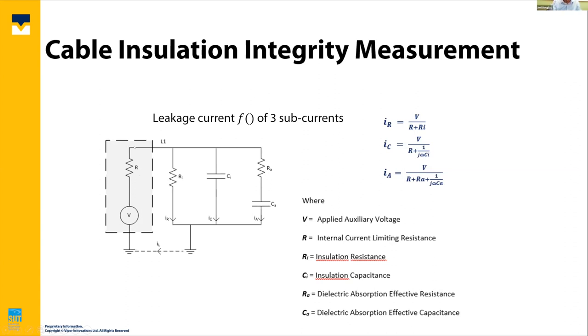current through this internal impedance between one of the conductors in the umbilical. So it's always connected to at least one conductor in the umbilical. I've called it L1 here, and ground, earth. So the IMD or LIM is connected between earth, the legs of the platform, and one of the conductors of the umbilical coming up.